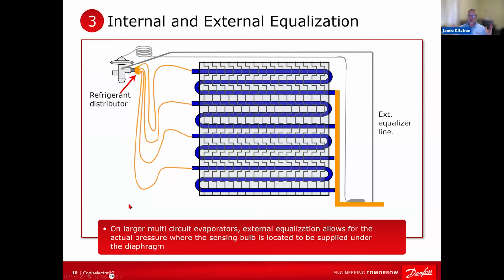They're all multi-circuited. If you have a distributor, you absolutely 100% need to use an external equalized valve, because here's why. Remember that pressure under the diaphragm? If you did not have that external equalized valve, if it was internal equalized, your TXV would think the pressure in the evaporator is what it is before the distributor. And that distributor might have a 15, 20, 25 pound pressure drop across it. It needs to, because it has to equally distribute all that refrigerant, hopefully equally. All right.